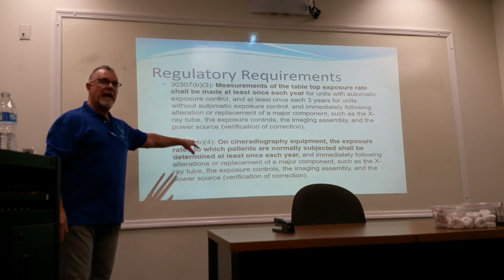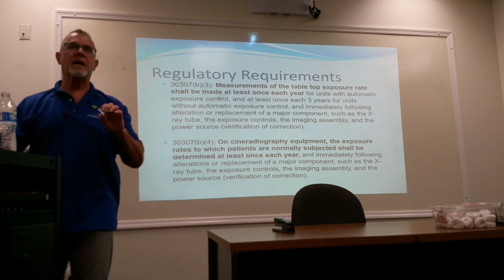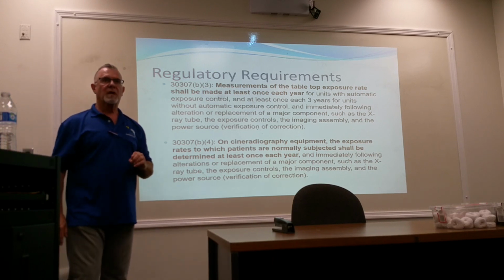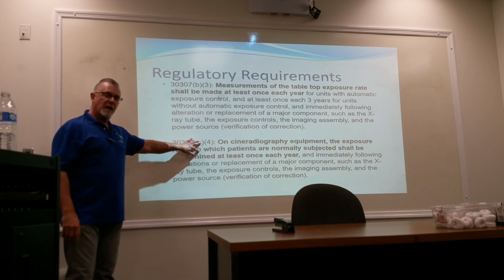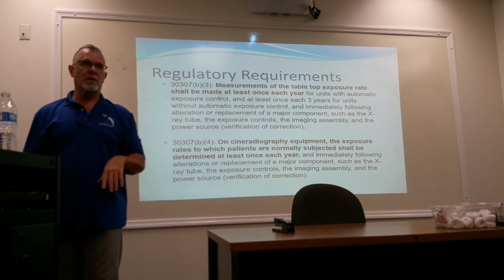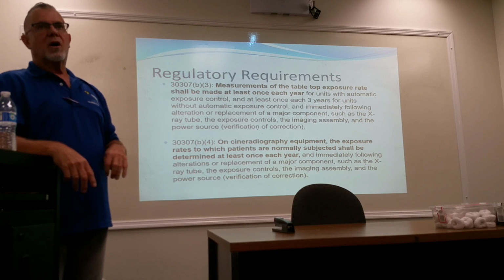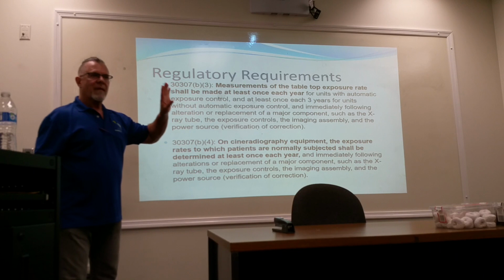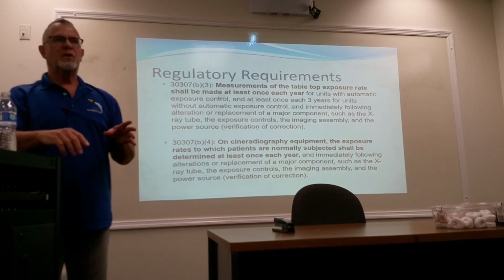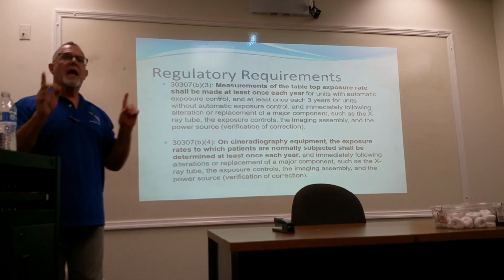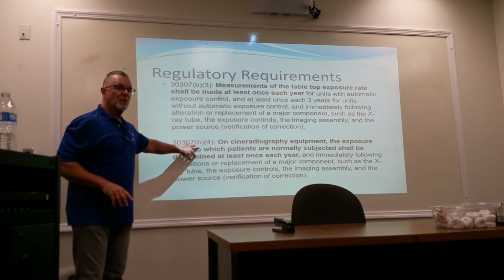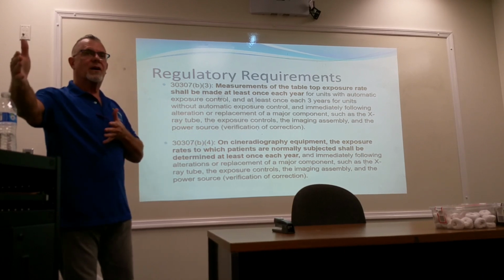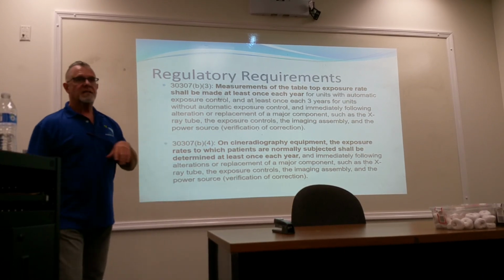If you look at cine in the old world, cine was 30 frames per second or 60 frames per second on 35 millimeter film. So you should consider that the same definition in the digital world. So after a year of hemming and hawing and finally doing that, they issued an interpretation that says, if the piece of equipment is capable of doing 15 frames, that's not pulse mode, that's images. So 15 images per second and higher, they consider that to be cine.